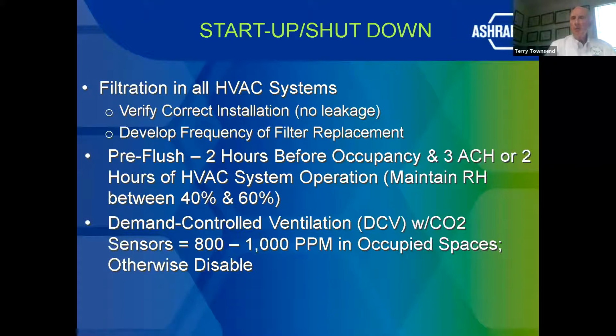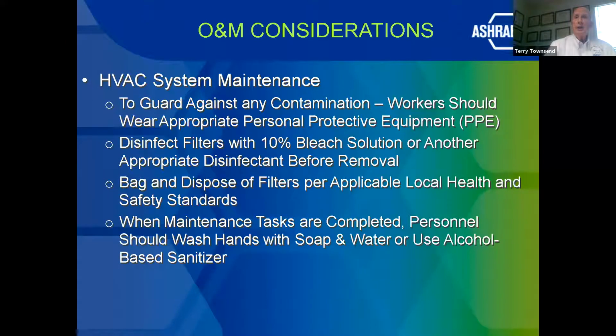The pre-flush is recommended 2 hours before occupancy, or achieving 3 air changes per hour for 2 hours of HVAC operation. But the key here is not just to turn it on and let it operate, but to maintain relative humidity between 40 and 60%. Demand control ventilation with CO2 sensors, if in occupied spaces, control between 800 and 1,000 parts per million. If they're not occupied spaces, disable demand control ventilation. So guard against any contaminations.